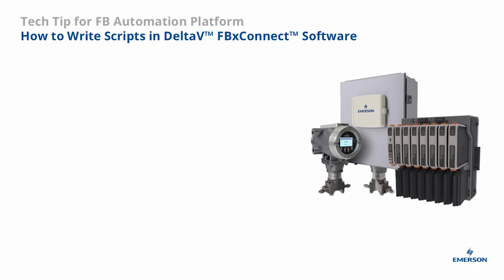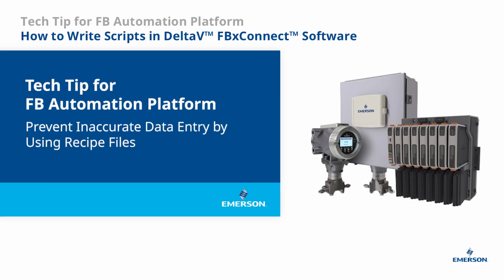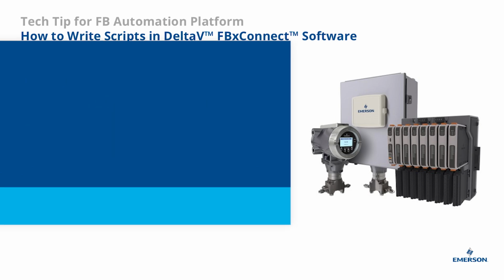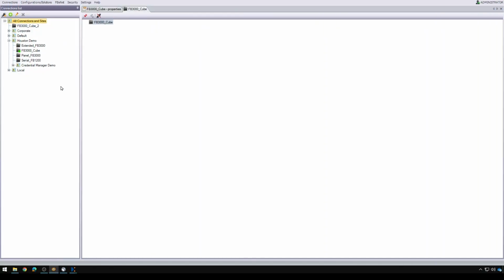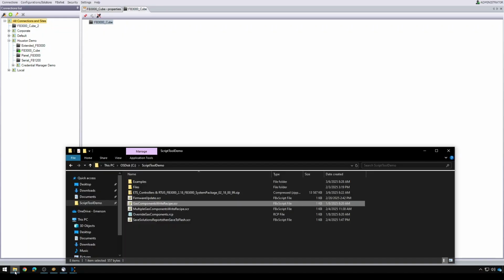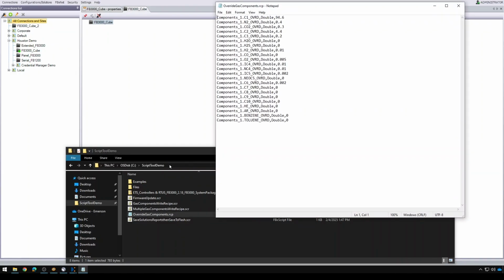Another example of how you can keep configuration consistent and prevent inaccurate data entry is to make use of recipe files. I'll open up a recipe file here. They've got an extension of .rcp, and they can either be read from a device or written to the device depending on your scripting commands. In this example recipe file, I've got the gas component override fields, then I've got their data type and the values I would like to write down to the end device.